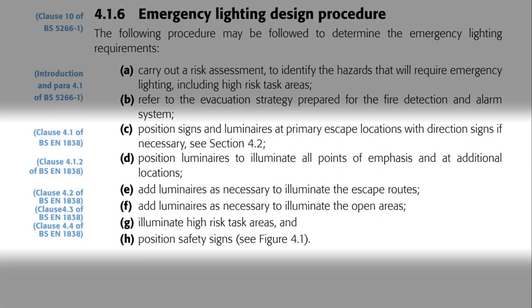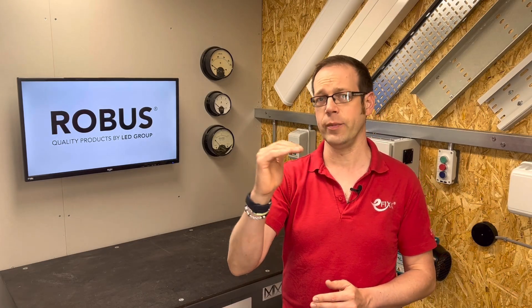C — position signs and luminaires at primary escape locations with direction signs if necessary, see section 4.2. D — position luminaires to illuminate all points of emphasis and at additional locations. E — add luminaires as necessary to illuminate the escape routes. F — add luminaires as necessary to illuminate open areas. G — illuminate high risk task areas, and H — position safety signs. Signs are given heavy prominence, particularly at escape locations, even being listed ahead of luminaires in indent C. Direction signs are critically important — more on that in a moment.